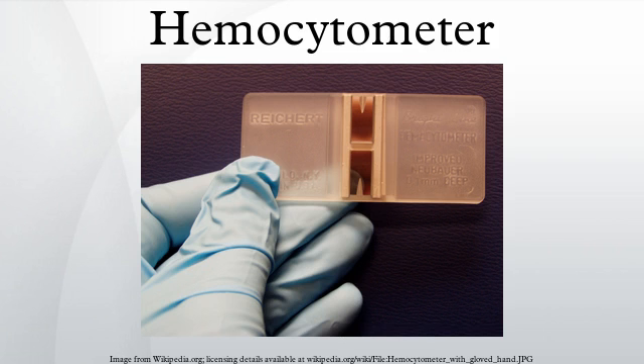The hemocytometer is a device used to count cells. It was originally designed for the counting of blood cells. The hemocytometer was invented by Louis-Charles Malassez and consists of a thick glass microscope slide with a rectangular indentation that creates a chamber. This chamber is engraved with a laser-etched grid of perpendicular lines. The device is carefully crafted so that the area bounded by the lines is known, and the depth of the chamber is also known. It is therefore possible to count the number of cells or particles in a specific volume of fluid, and thereby calculate the concentration of cells in the fluid overall.